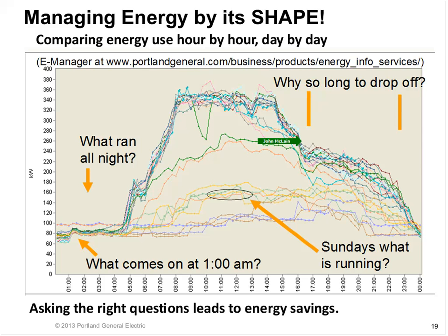What they were doing is they turn all the lights on in the building, and as they finished cleaning a room, when they left, they would turn them off. And so that was their way of keeping track of what rooms had been cleaned. Obviously, when you look at the graph, you went, wow, that's not what I want. I'd rather have something where they turn the lights on only in the rooms they're cleaning rather than turn them off as they leave. And that would change the shape to something that looked more like this, which is something you'd want.